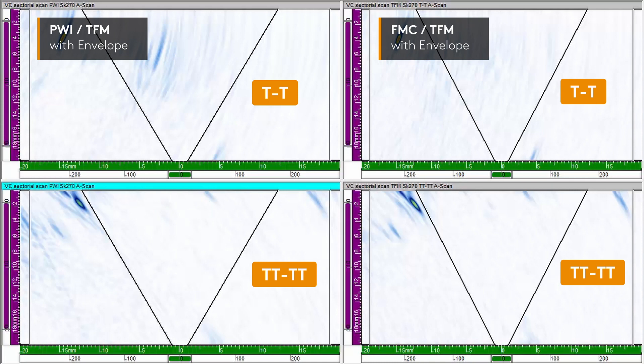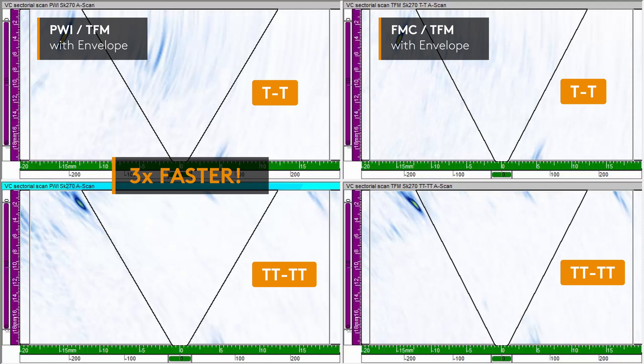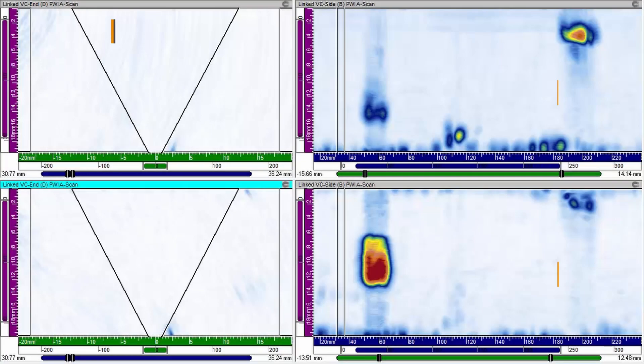With the new Emerald Phase Array unit powered by UltraVision, a code-compliant encoded inspection with live two-sided PWI and both reconstruction modes can be performed at 60mm or more than 2 inches per second. This is three times faster than with regular FMC TFM.